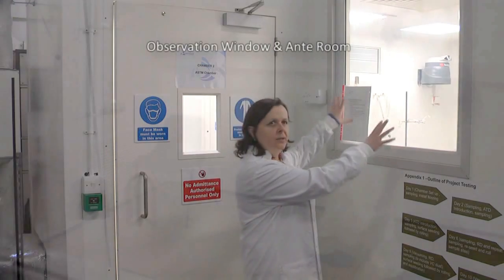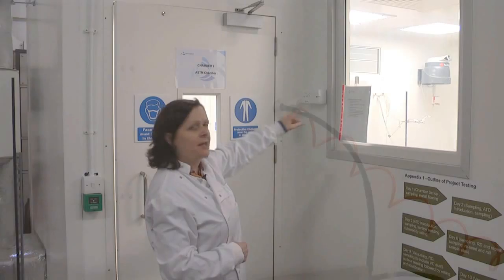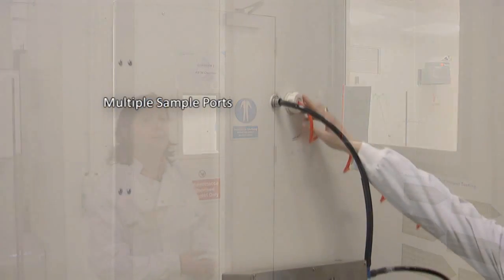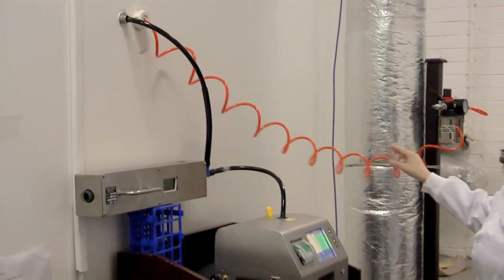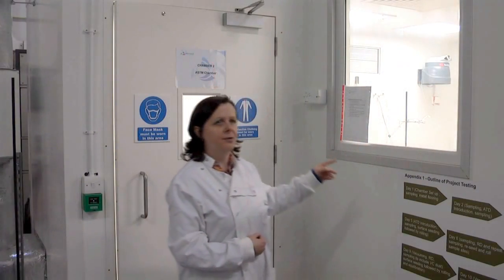In addition to this window here where you can observe everything going on in the chamber, we also have an ante room which is positive pressure. This prevents cross-contamination between what's going on in the chamber and outside in the environment. We have a number of sample ports in the chamber, so we can take air samples, monitor particle counts, and measure airborne allergen and airborne microorganisms.